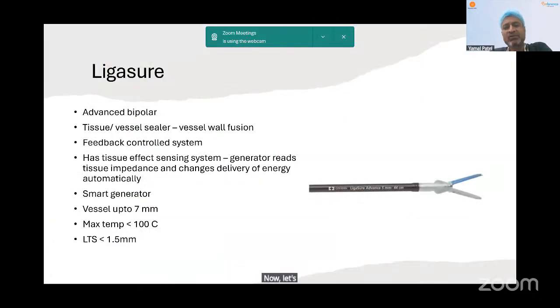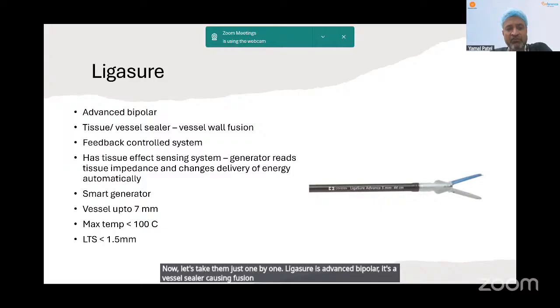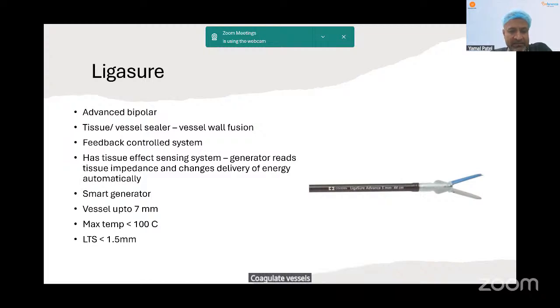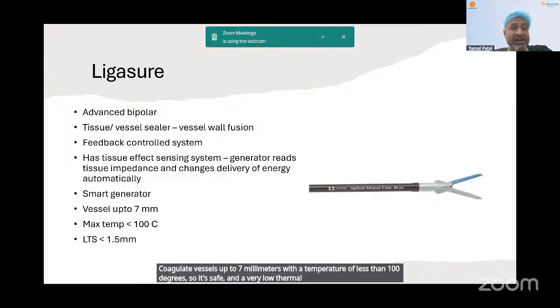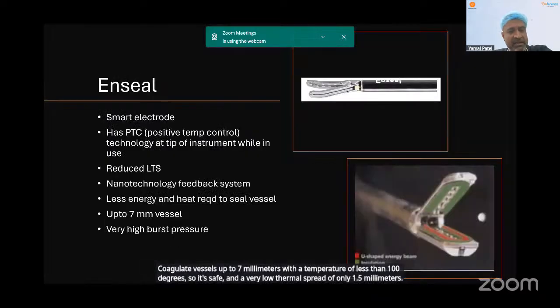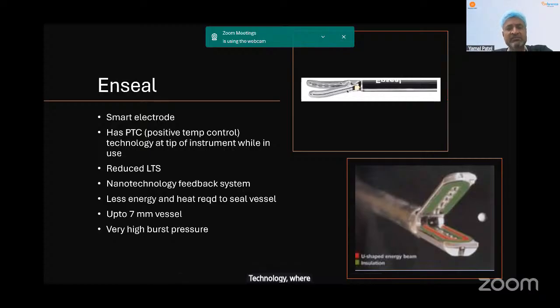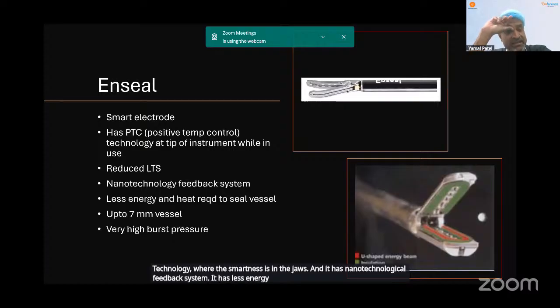Now, let's take them one by one. LigaSure is advanced bipolar. It's a vessel sealer causing fusion. It is feedback controlled. It has tissue sensing and activity. It is a smart generator that gives you audible feedback. It can safely coagulate vessels up to 7 millimeters with a temperature of less than 100 degrees. So it's safe, with a very low thermal spread of only 1.5 millimeters. Enseal, on the other hand, is also a smart electrode-based technology, where the smartness is in the jaws. It has a nanotechnological feedback system. It requires less energy and heat.